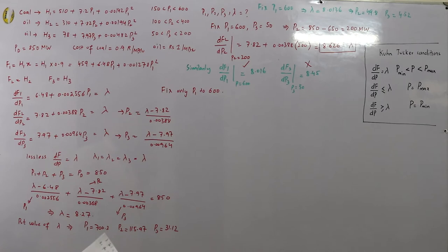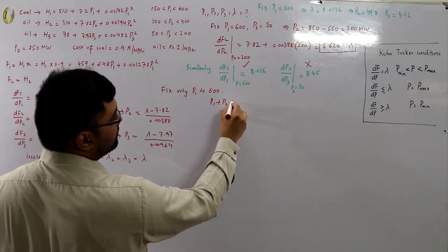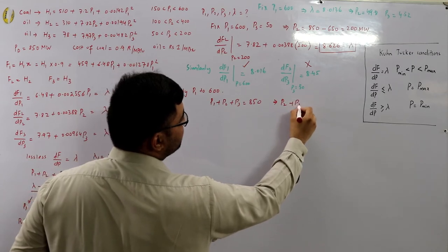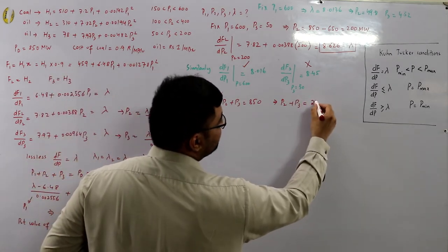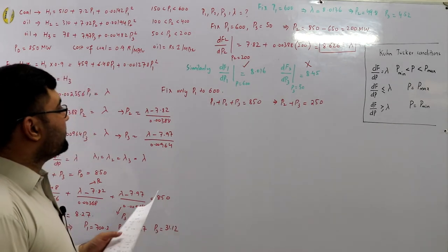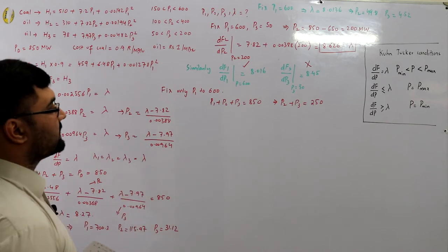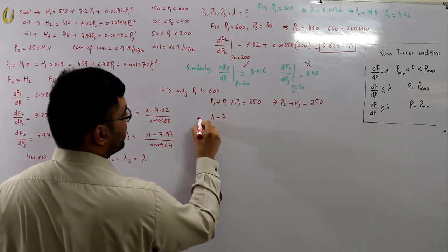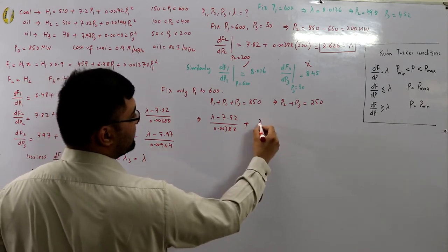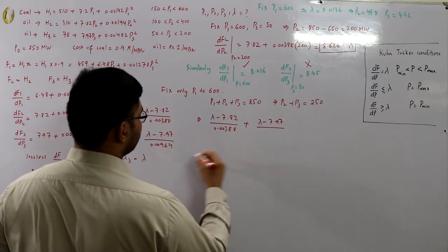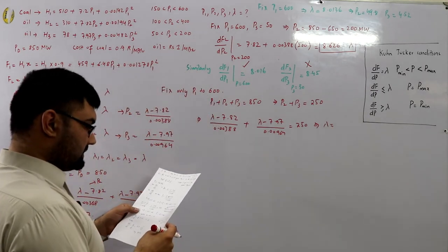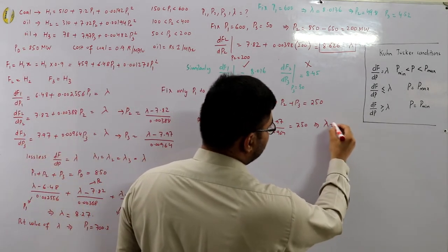With p1 = 600 MW fixed, the remaining demand is p2 + p3 = 850 − 600 = 250 MW. Substituting the expressions: (λ − 7.82)/0.00388 + (λ − 7.97)/0.00964 = 250. Solving gives λ = 8.57.